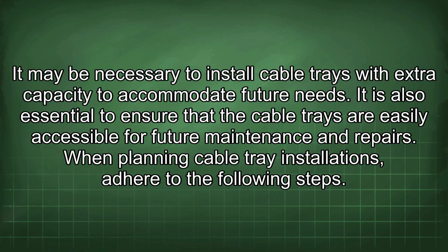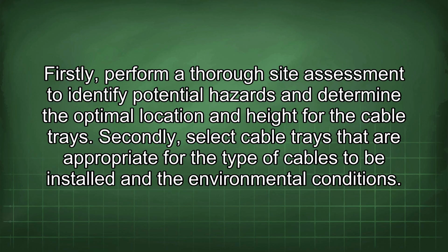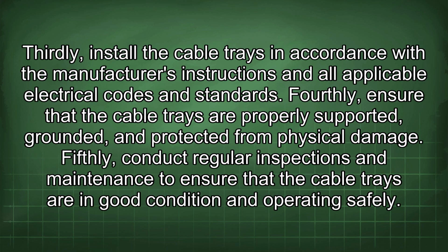When planning cable tray installations, adhere to the following steps. Firstly, perform a thorough site assessment to identify potential hazards and determine the optimal location and height for the cable trays. Secondly, select cable trays that are appropriate for the type of cables to be installed and the environmental conditions. Thirdly, install the cable trays in accordance with the manufacturer's instructions and all applicable electrical codes and standards. Fourthly, ensure that the cable trays are properly supported, grounded, and protected from physical damage. Fifthly, conduct regular inspections and maintenance to ensure that the cable trays are in good condition and operating safely.